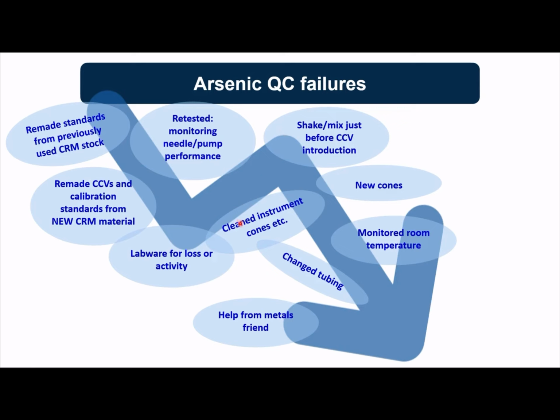And then kind of moved on to cleaning the instrument, the cones, some of the other parts. I believe new cones were considered, and I think they were swapped out at some point. The tubing was changed, and then it was a new facility, and there were some fairly large swings in the room temperature at the time. HVAC, some issues cropped up, and maybe the AC wasn't working as well as it needed to on certain days. So that was a consideration as well.